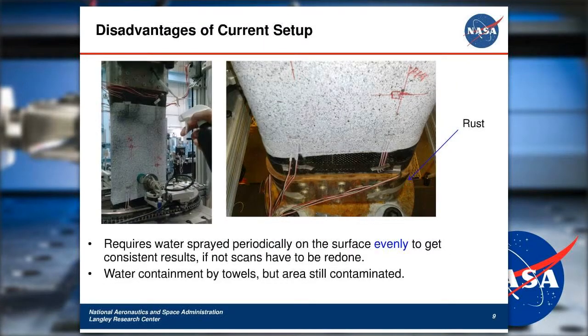Okay, the disadvantage of this current setup is that, even though you have this water balloon tip on the end of this measurement system, you have to apply water to the surface. Normally an operator is squirting water on the surface. The water has to be sprayed evenly to get consistent results. If the water is not sprayed evenly, then the scan will have to be redone. Sometimes you have to have two operators, one who's spraying the water, and the other watching the signal on a computer screen, making sure the signals are uniform and that you don't have to redo the scan.